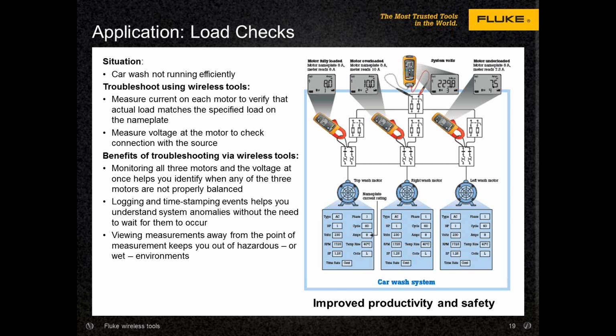It also gives you an idea whether your breaker ampacity is set or established properly for the startup, because if you put on a motor that's got too much startup current and a breaker that's not rated for that kind of startup, you're going to have trips that will drive you crazy. Okay, so if you have a lot of nuisance tripping in a situation, you may be able to use that function to help you isolate it. Yeah, that's where the logging really comes into play with some of this stuff.